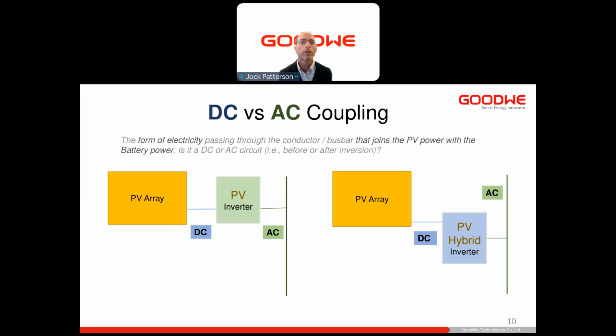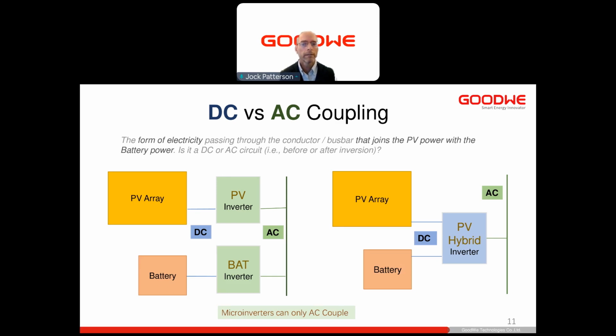With terminology, there are a lot of familiar words, I just want to make sure we're on the same page. For DC and AC coupling, imagine two identical PV arrays: one connected to a PV inverter, just a grid-tied inverter, and the other to a PV hybrid grid-interactive inverter. They both receive the same power from the PV array, but to add a battery to the system on the left, you need a second inverter, a battery inverter, which brings that power into the battery. So the PV array to battery connection is through an AC circuit on the left, and through the DC bus inside the PV hybrid inverter on the right. That's DC and AC coupling. Note that microinverters can only AC couple because they are PV inverters.